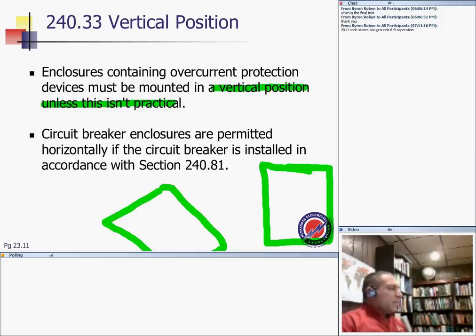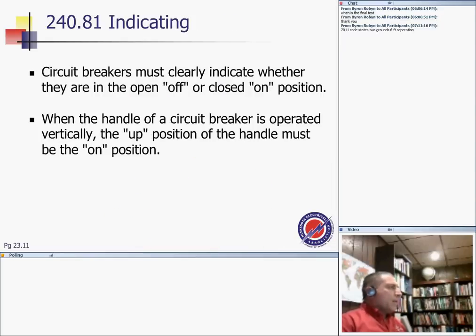Circuit breakers are permitted horizontal if the circuit breaker is installed in accordance with some exception. Can I put my circuit breaker horizontal? Yes. There are some exceptions and restrictions on that one. If in the vertical position, off is down and on is up, always. Up is on, so down is off.